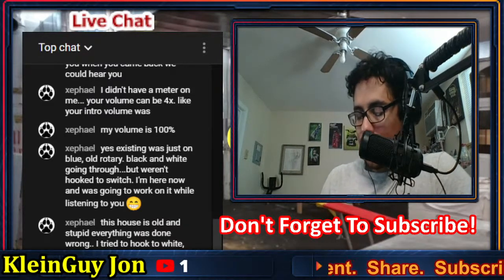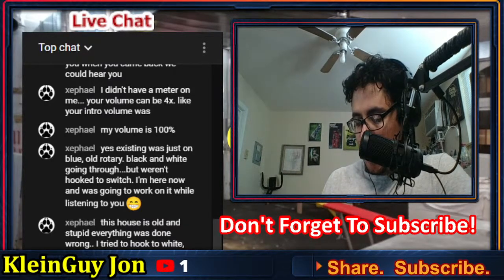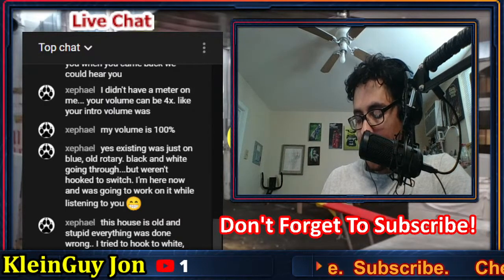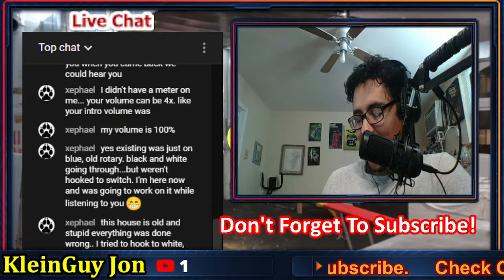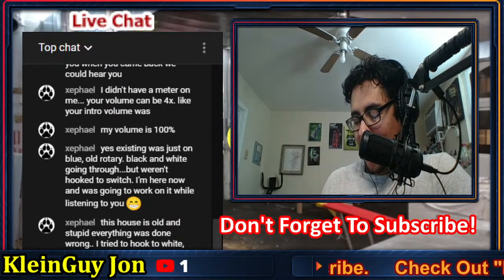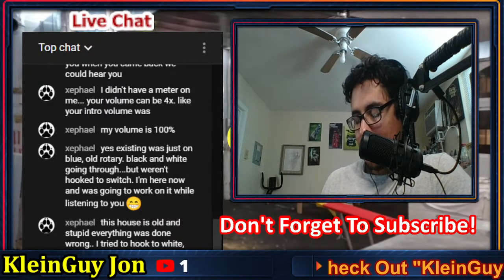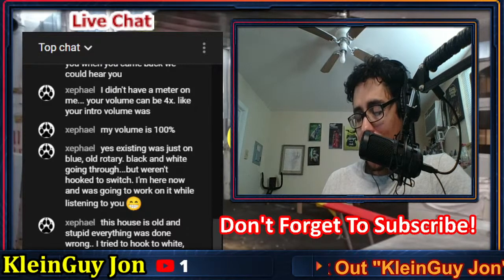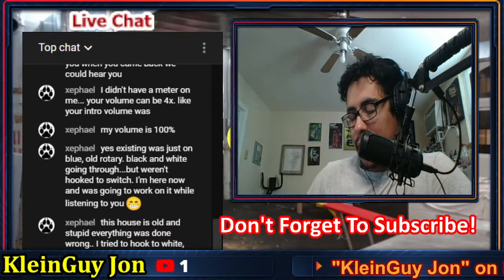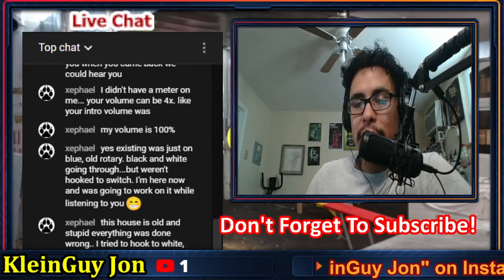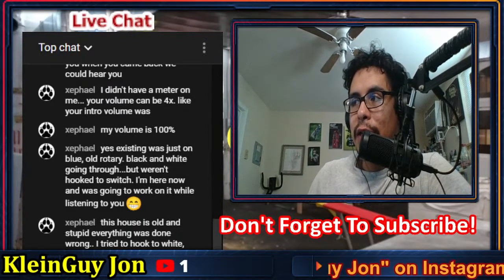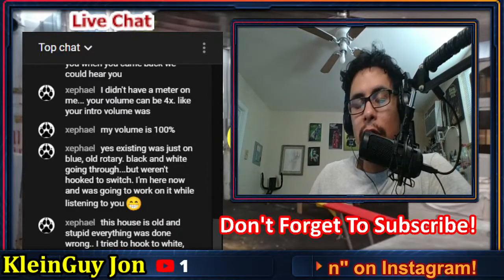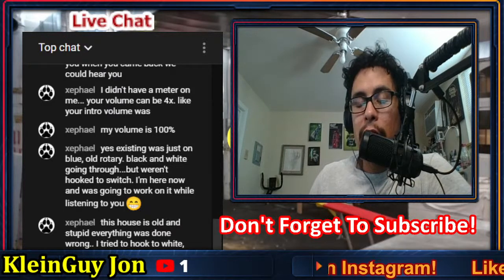Let's see here. Zaphael says this house is old and stupid. Everything was done wrong. I tried to hook to white, and lights came on bright, and the switch shut off with the dimmer. Well, in that case, if you can't tie it to an existing neutral, tie it in separately as a dedicated neutral.